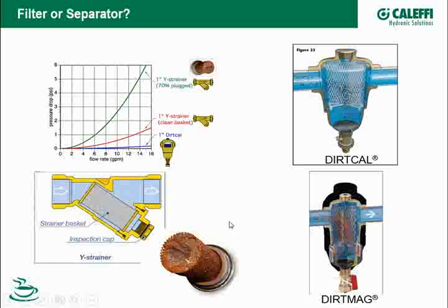If you've got an old system that has a lot of dirt and rust, like a cast iron radiator system or an old iron pipe system, the strainer can protect it, but you've got to protect the strainer, so to speak. I think a better way of doing that is with a separator. We make a lot of different types of these, some with magnetic bands, but basically the difference is with a separator, you're causing the particles to fall down to the bottom where they're out of the fluid stream, so you're not plugging up the flow going through it.